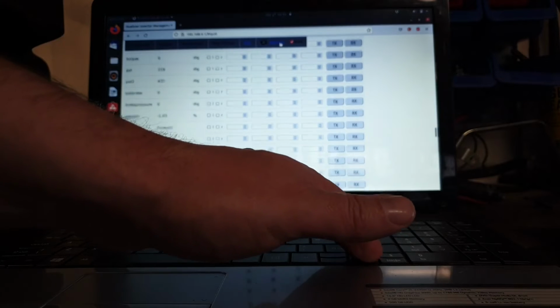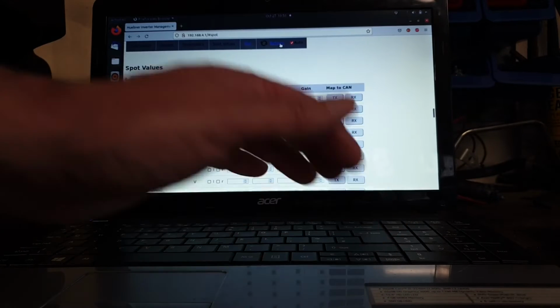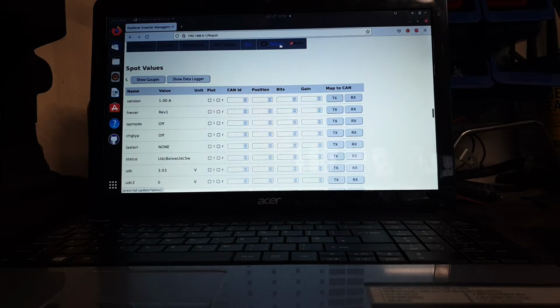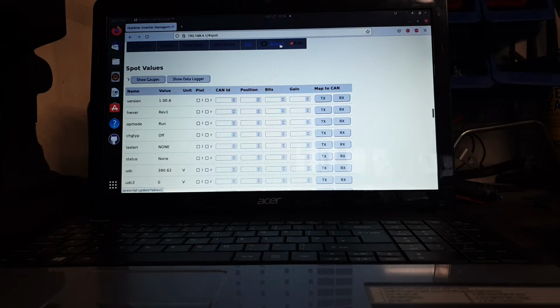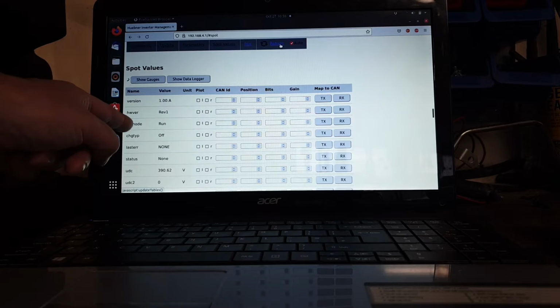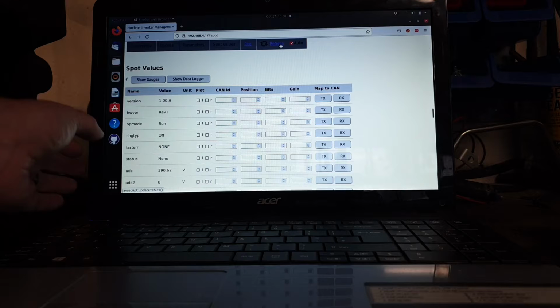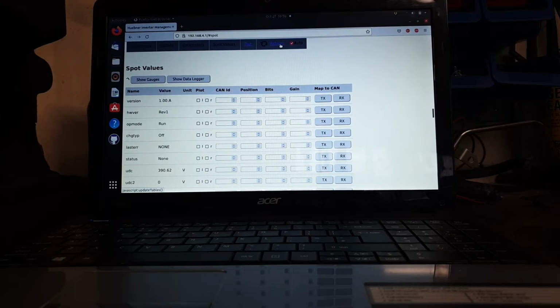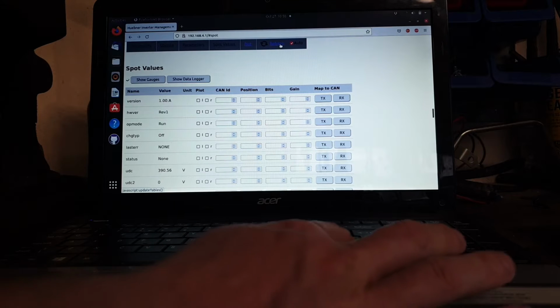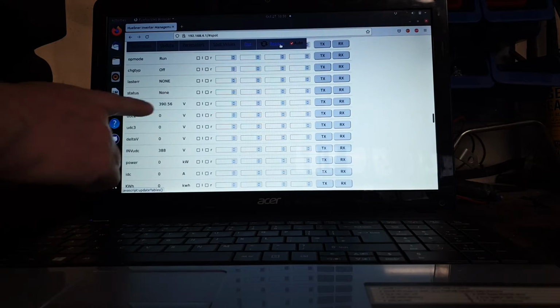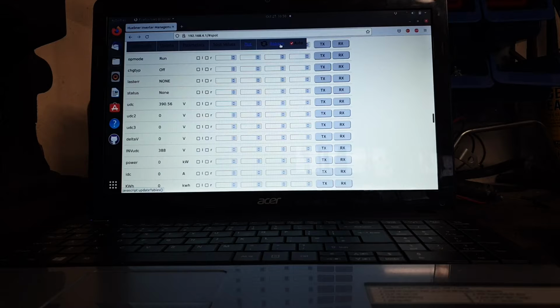So we're going to go back up to the top of spot values here, and I'm going to hit my start button. Now you see here that op mode has changed to run, last error is still none, and status is now none, which means we have no errors and no status problems. We're seeing the full 390 volts available here in UDC.